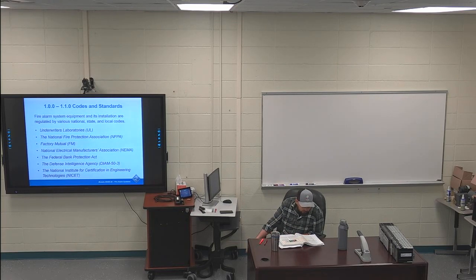So it's for equipment. The last bullet point in that section before 120 is highlighted, the National Institute for Certification in Engineering Technologies. This is not a commonly known standard, at least in a lot of fields. But this establishes standardized testing of fire alarm designers and installers. You can't just be a random person and go install fire alarms in buildings. You have to be certified in order to do that. And the NICET establishes those tests so that people can get certified to install this stuff.